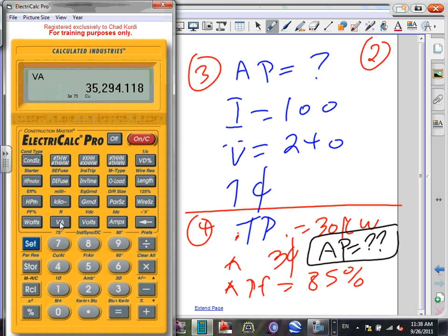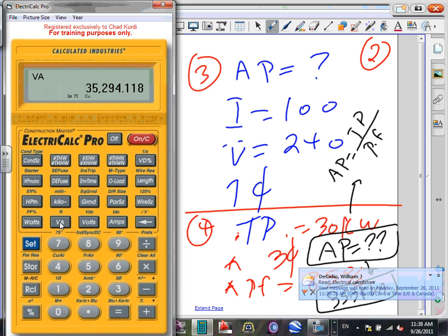Is that true? If you use your calculator and divide, the formula for this, as you and I know, is apparent power equals true power divided by power factor. So if you take the 30K divided by 0.85, you're going to end up with 35.3, which is right here. You end up with this value equal 35.3 kVA. Done. See how easy that is, nice and clear cut.